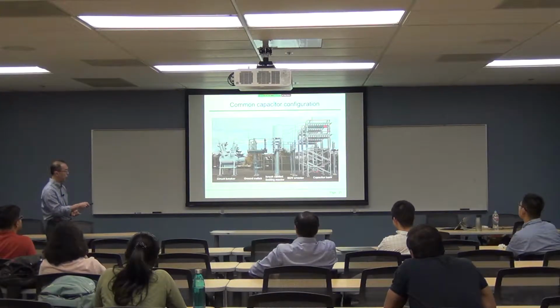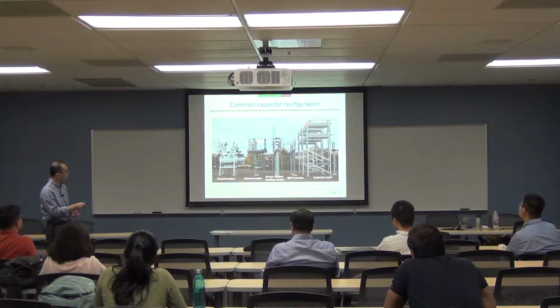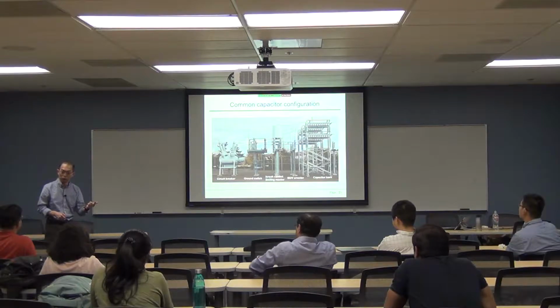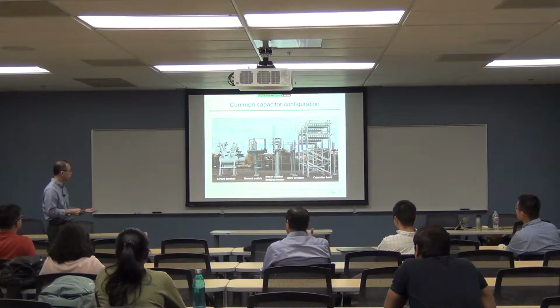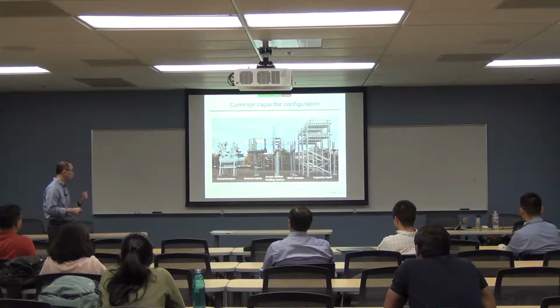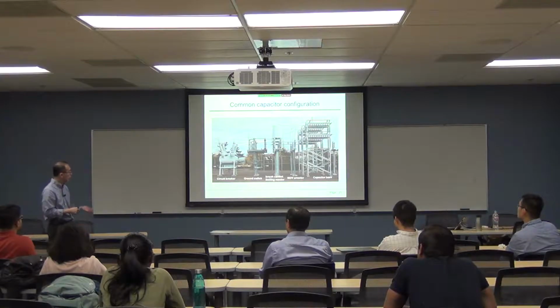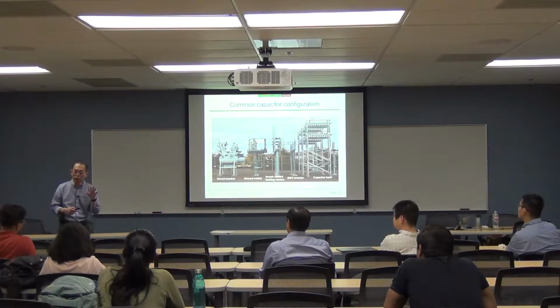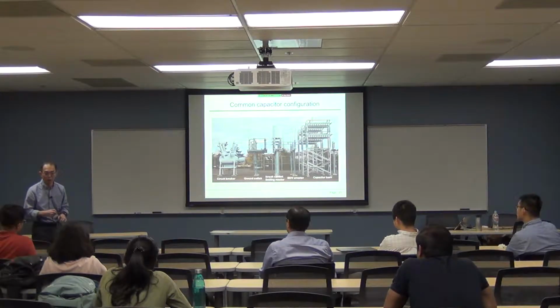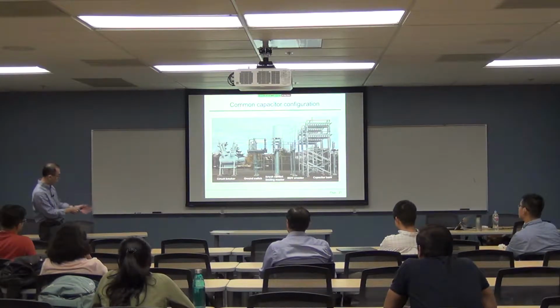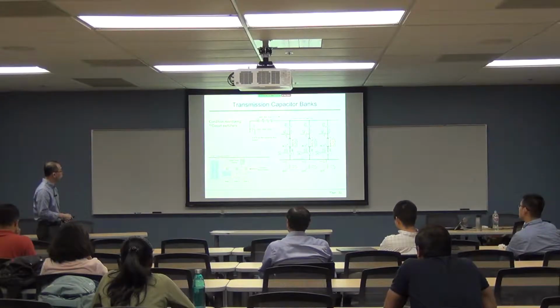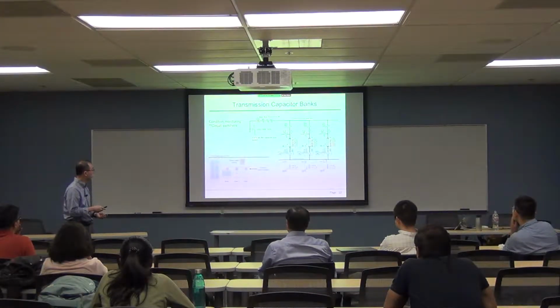You can see this is the capacitor rack, with phase A, B and C. In each phase you can see there are rows and rows of capacitors in here. So each capacitor unit could be protected externally or internally by a fuse. And then you have this arrestor, I think you know what that is. Inrush current limiting reactor, a ground switch, and a circuit breaker. People don't really use circuit breakers these days, most of them use circuit switchers to energize or de-energize the capacitor bank. So this is like the circuit switcher in here, and you might have a circuit breaker behind it. Now this is an actual view of a transmission capacitor.